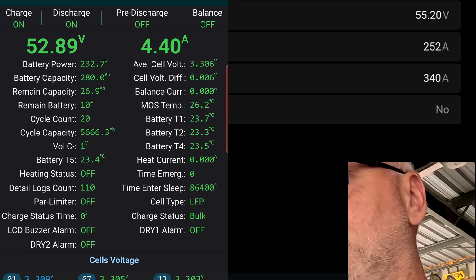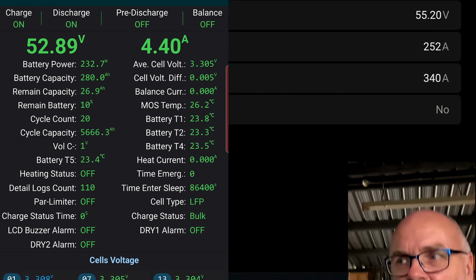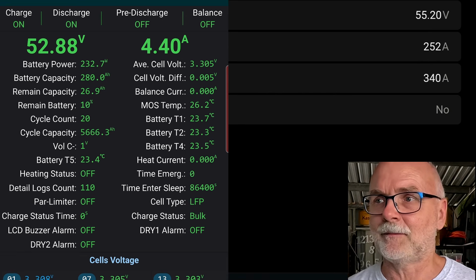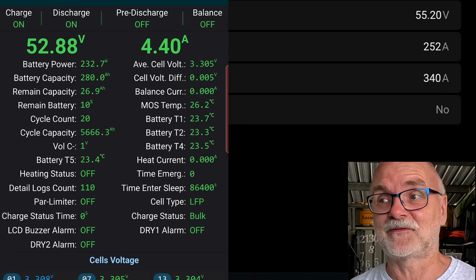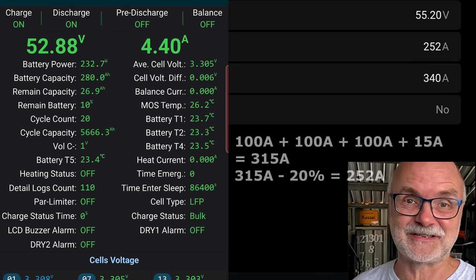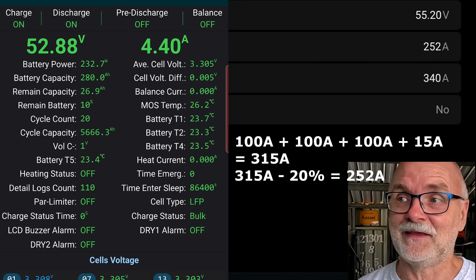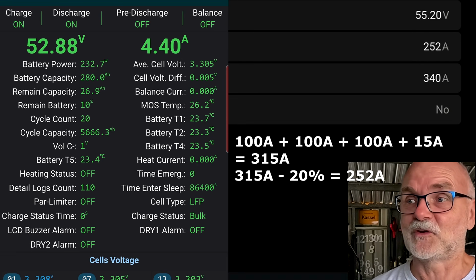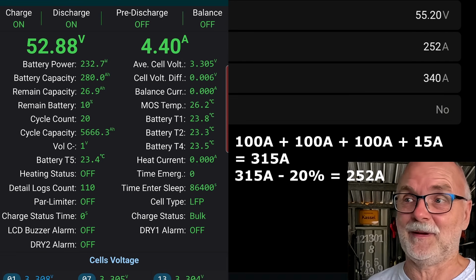And now we should also see the CCL increasing again because the fault has cleared. So the CCL should go up to 320 amps. In this case it doesn't, because we have changed the charge current here in the BMS to only 15 amps. So 252 is the maximum for this setup at the moment, for this test setup. Yeah. But usually you have 100 amps and go over 100 amps and then it reduces it to 10 amps only. And this fault is then sticky until you go under 5 amps with this particular BMS. And only this clears then the fault and gives you back the full charge current limit.